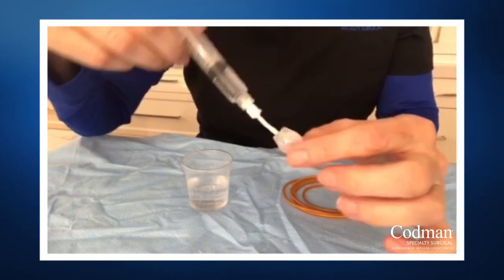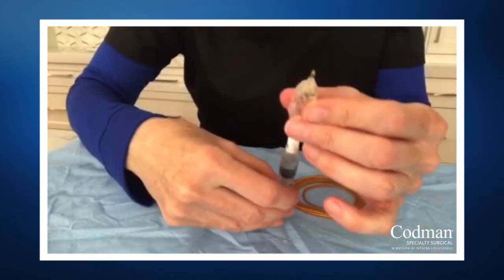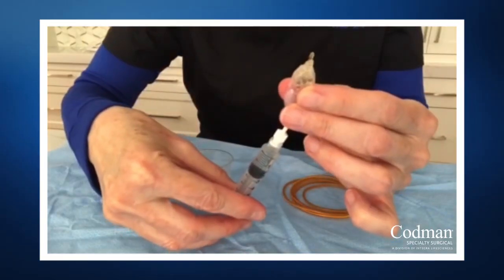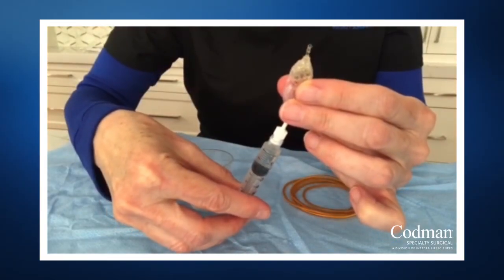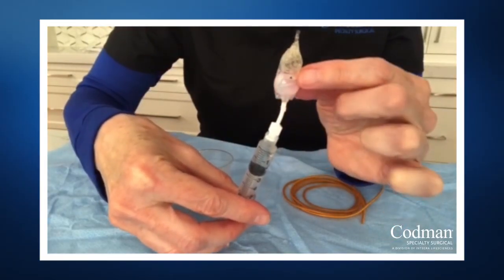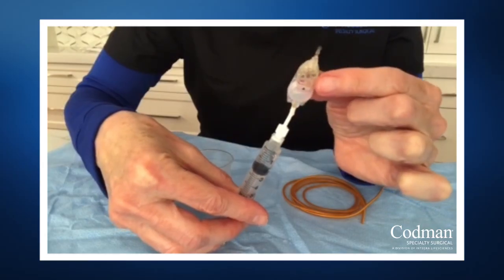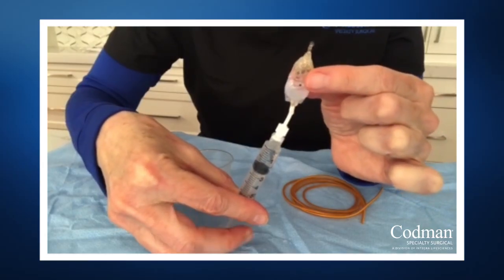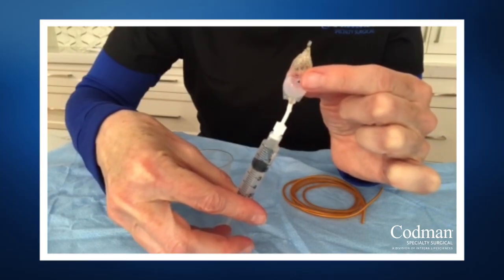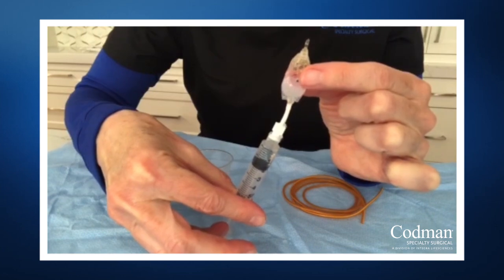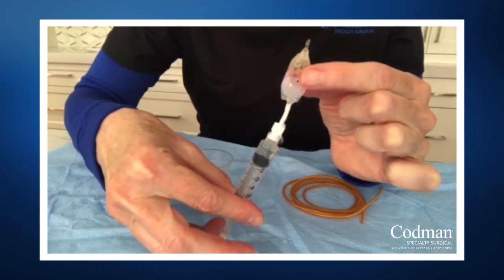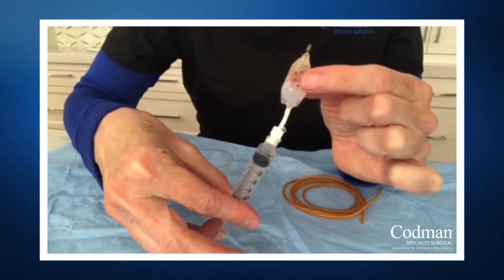So once I have fluid, then I'm going to take my valve and I'm going to invert it, and then I'm going to continue to prime, and you can see the air bubbles that are pushing through that's in the system. And then once I get a steady stream of flow out of the valve and all my air bubbles are gone, then I'm primed and it's ready for implantation.